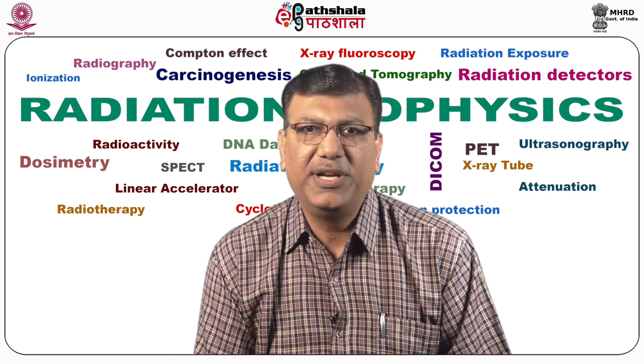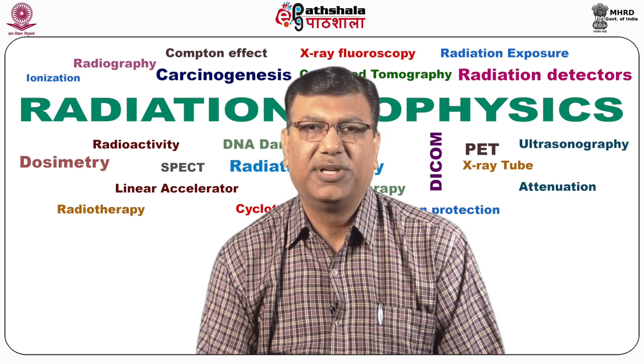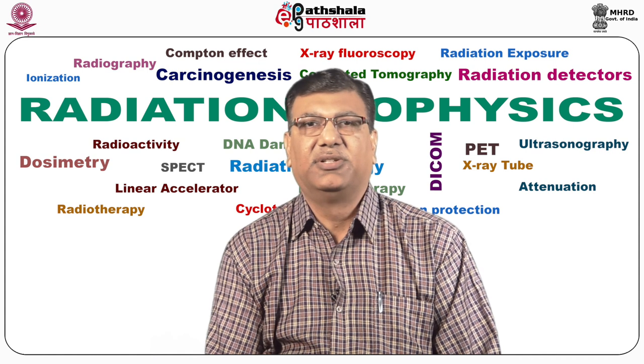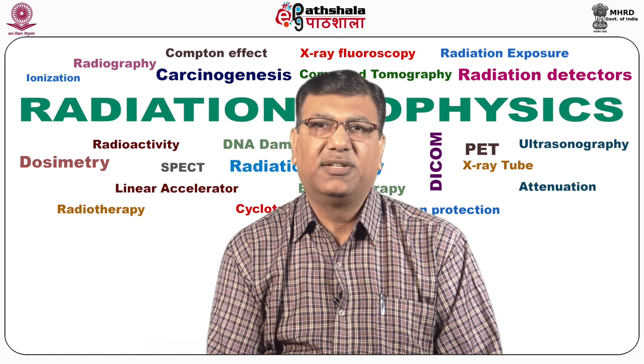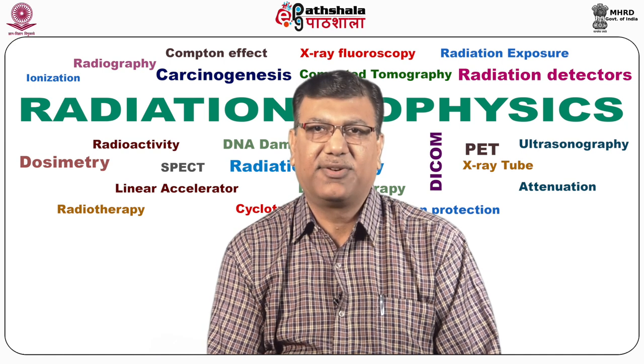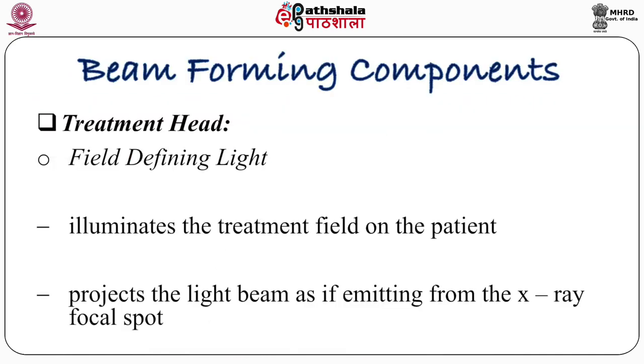The treatment head also contains a field defining light which illuminates the treatment field on the patient. We have to make sure that the radiation field and this optical light coincide with each other. It projects the light beam as if emitting from the X-ray focal spot — it is identical to the X-ray beam — which makes the treatment more accurate. We are able to see visually where the X-rays are falling on the surface.